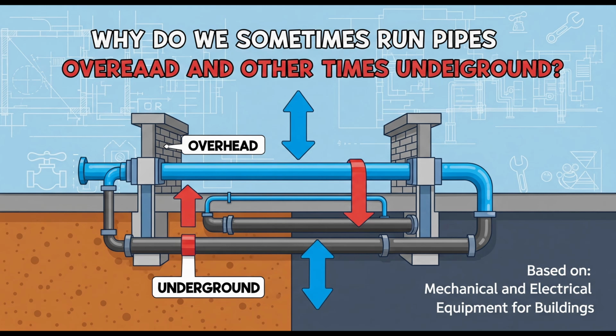And does the material affect how it's installed? Like overhead versus hidden? Definitely. And crucially, how it needs to be supported. For instance, plastic pipes are much more flexible than metal ones. So plastic PEX systems need supports much closer together to prevent sagging over time. Our source shows examples maybe just simple metal straps nailed to wooden joists if it's in a ceiling space. Metal pipes, being more rigid, can span longer distances between supports.